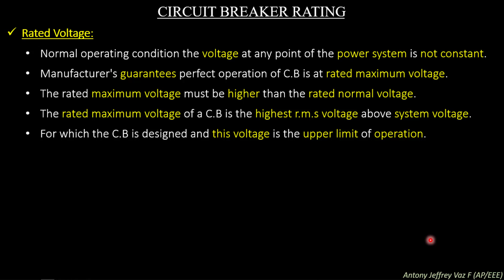The rated maximum voltage of a circuit breaker is the highest RMS voltage above system voltage for which the circuit breaker is designed, and this voltage is the upper limit of operation. So the highest RMS voltage should be the maximum rated voltage, so that the upper limit of operation is also the rated maximum voltage, and more than that it should never go. If it is more than that, then the circuit breaker will fail.